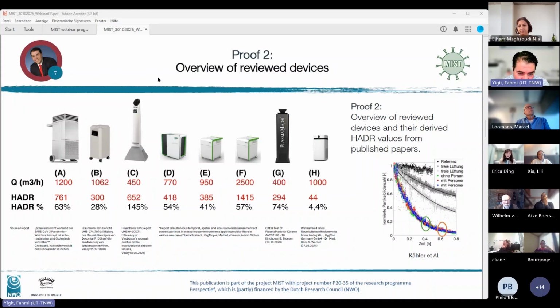So our link in this case is that we noticed, for example, that these three devices D, E, F had multiple positions in the room, and for every position there was a different hygienic air delivery rate value. That's normal because the fluid dynamics change based on the position and the interior settings. I'm fully with you, but in this case we asked the manufacturer: this is our mock-up, you tell us where to position your device, and then we will test it. But the biggest message here is: let the device do the work and don't help it with additional mixing or homogenization ventilators. That's the message.